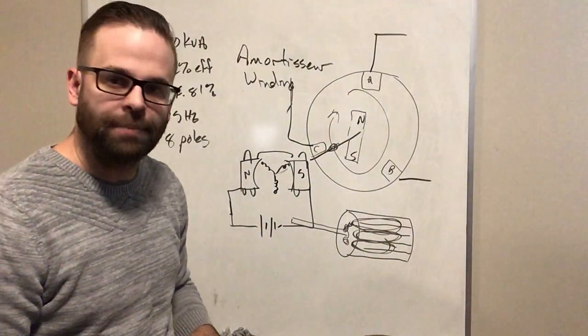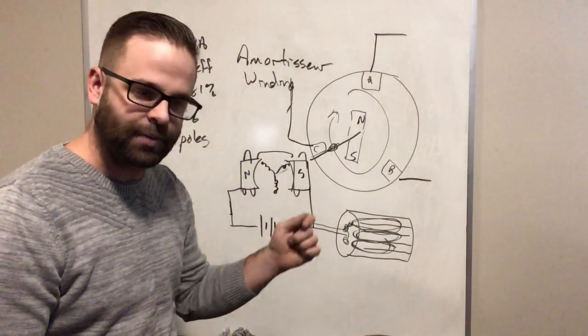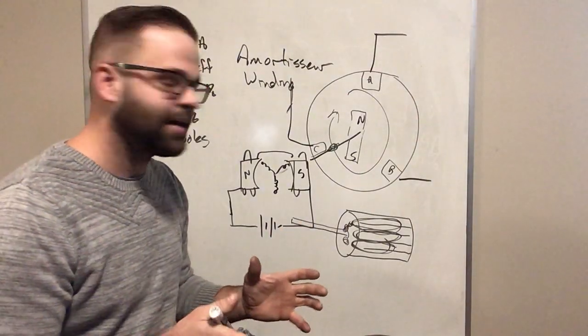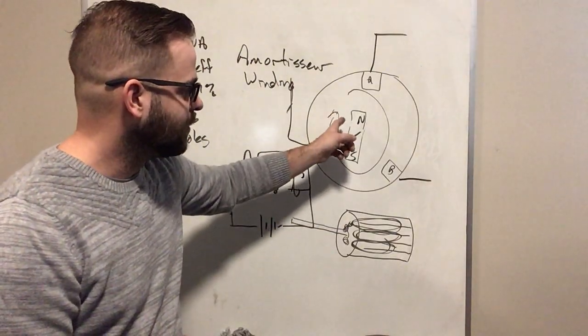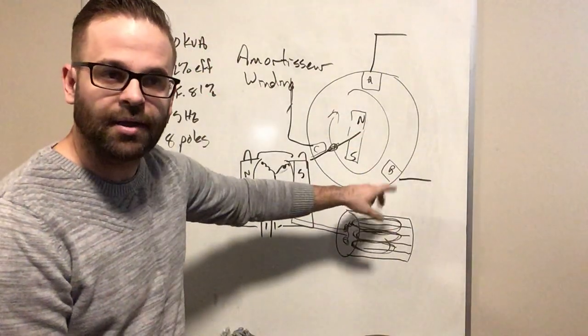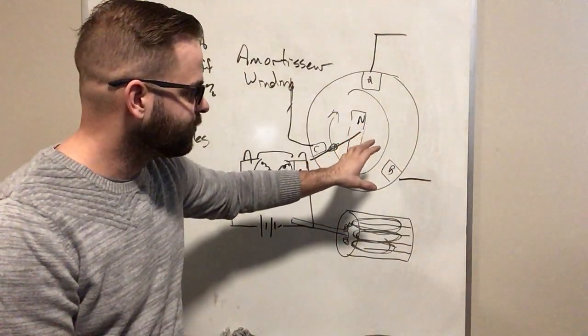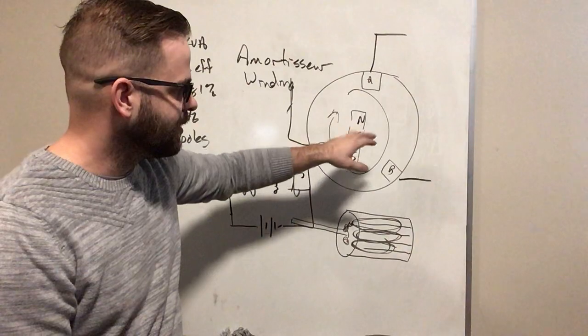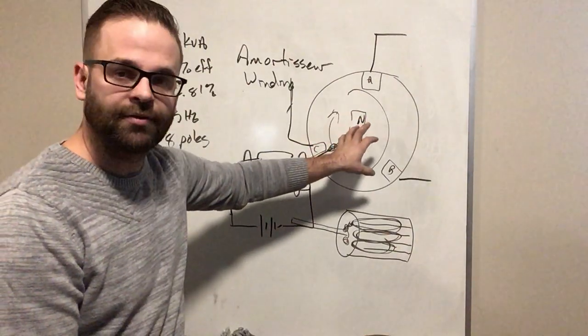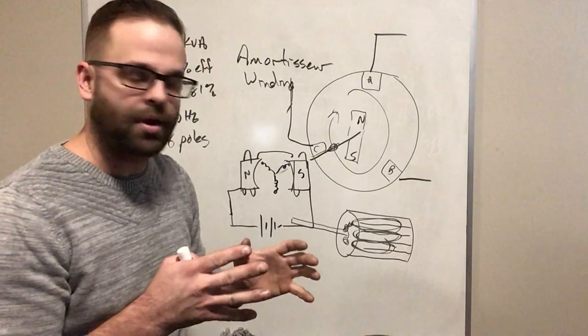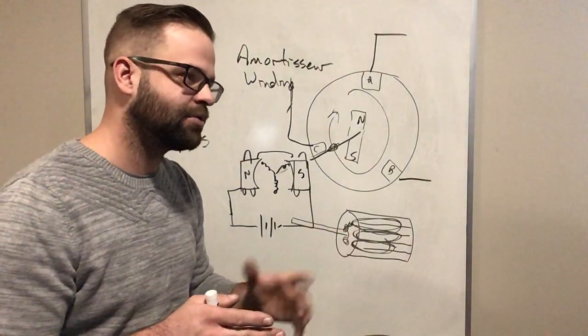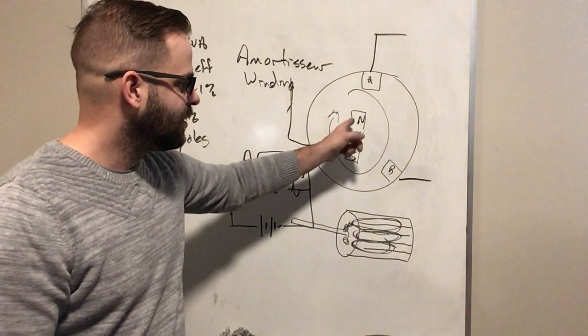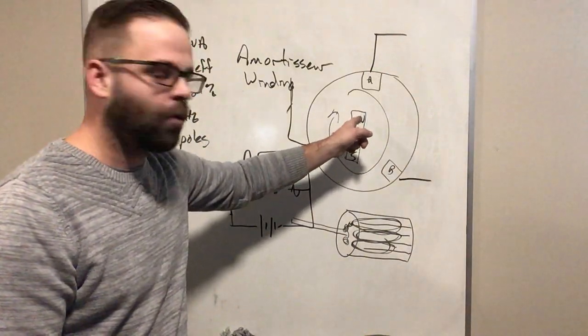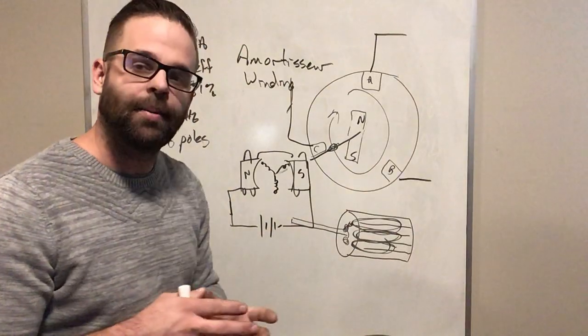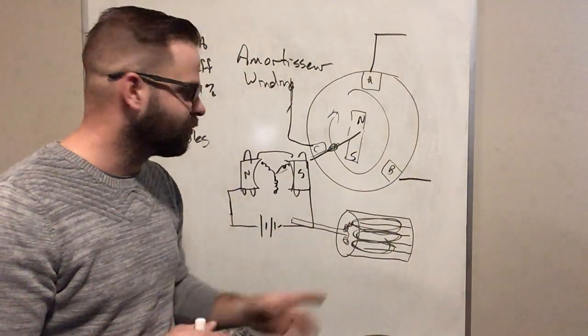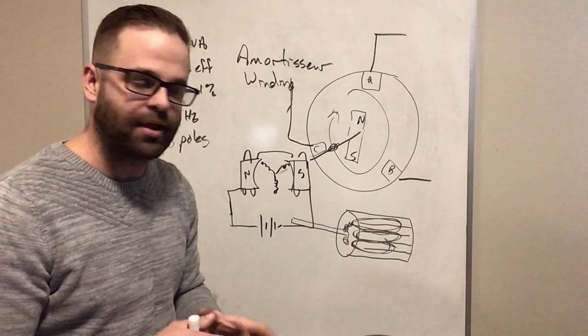And that's when we get that bump where it goes boom once we go to flip it on, and that's the two fields getting locked together. So our rotating magnetic field around the outside in the armature and the rotating magnetic field of the shaft now both have strong magnets, and because there's not a huge amount of relative motion between the two, that pole now can become in sync with the rotating magnetic field, so now they'll be synchronized together.